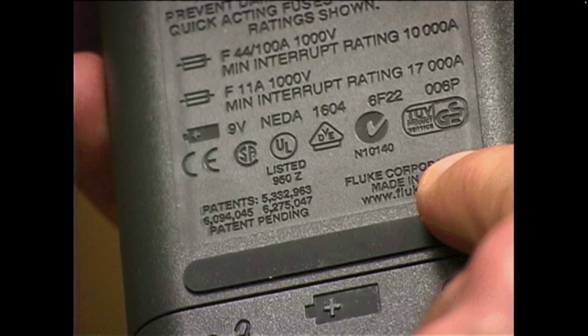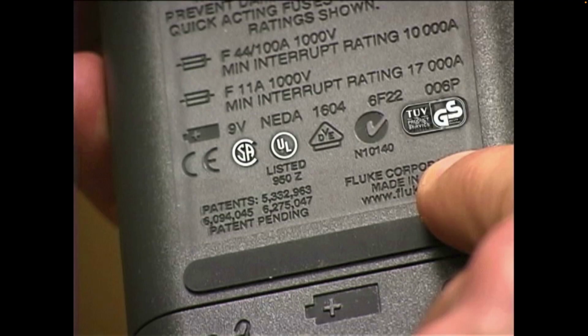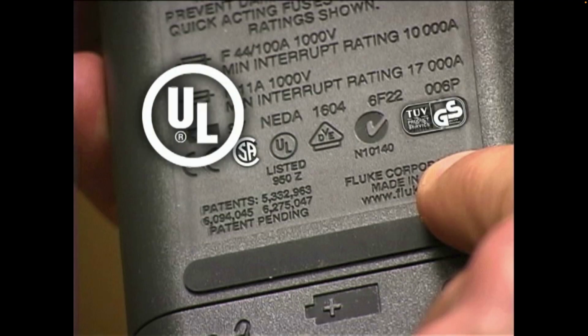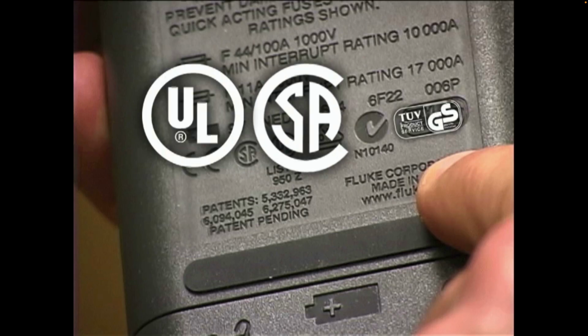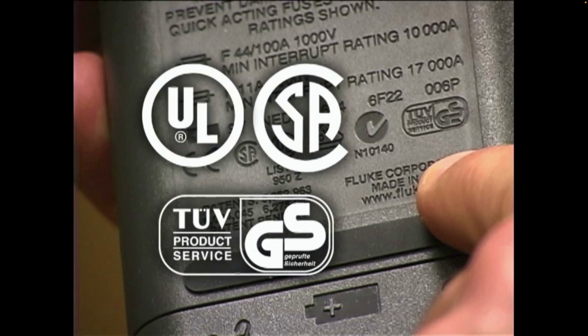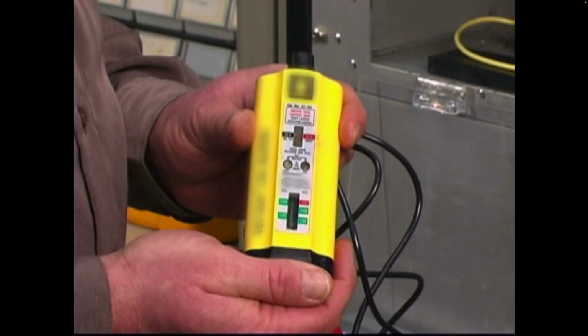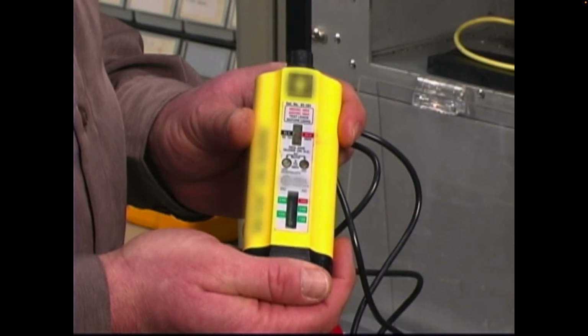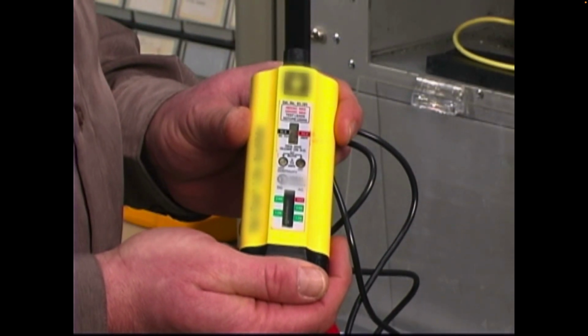That's why it is essential that the tester you use is labeled to show it has been certified by 2 or more independent testing laboratories, such as UL in the United States, CSA in Canada, and TUV in Europe. This is the only way you can be sure your testers have passed the most rigorous tests and meet every applicable standard. Here's what can happen when a meter marked Cat 2 is used in a Cat 3 environment.